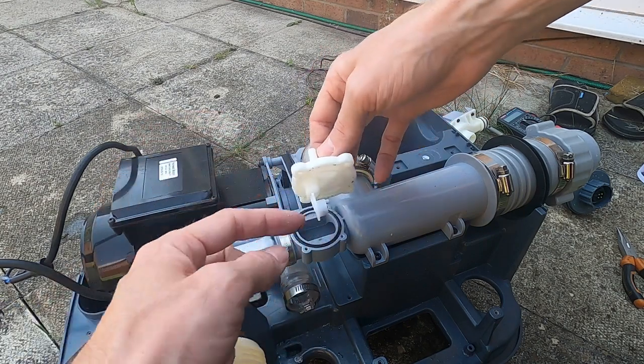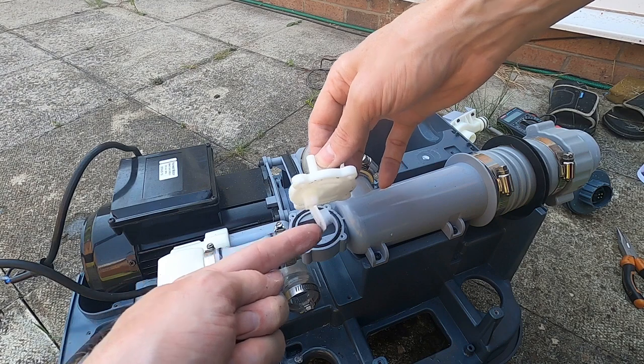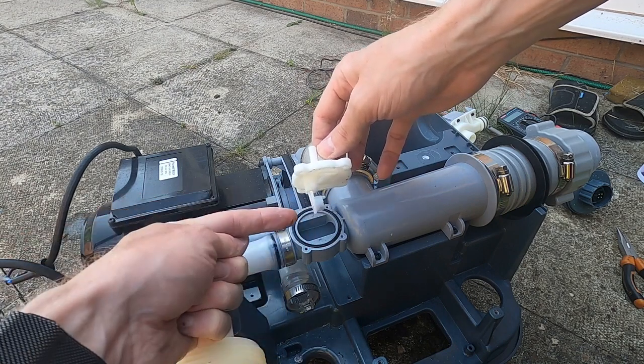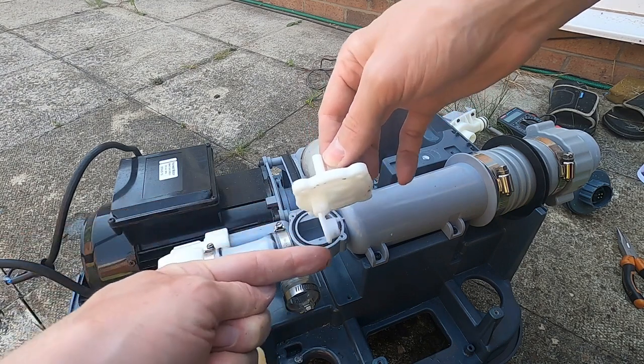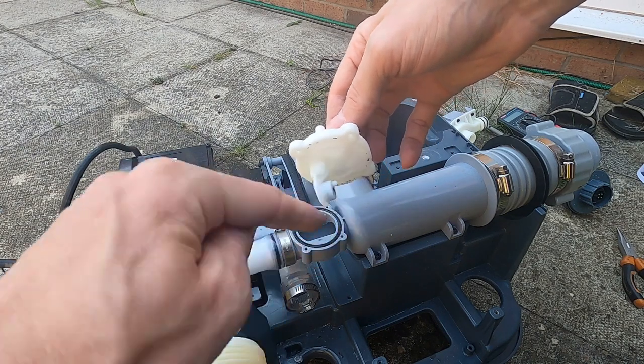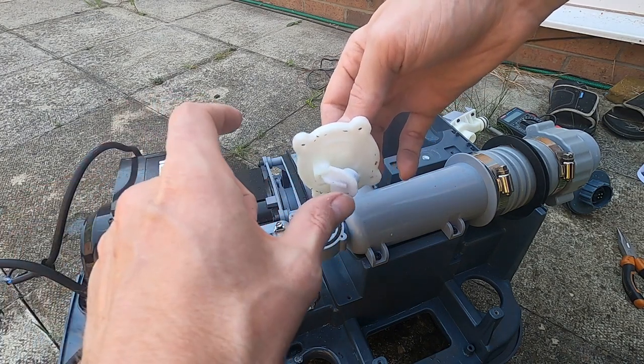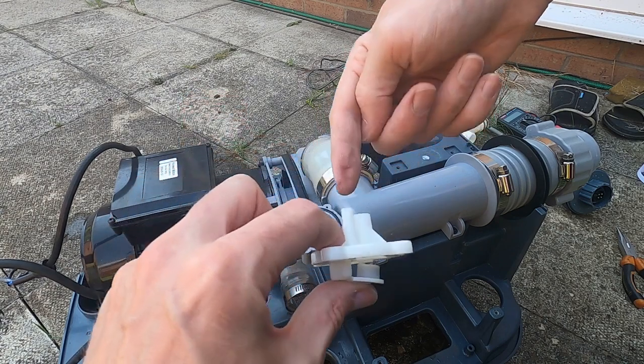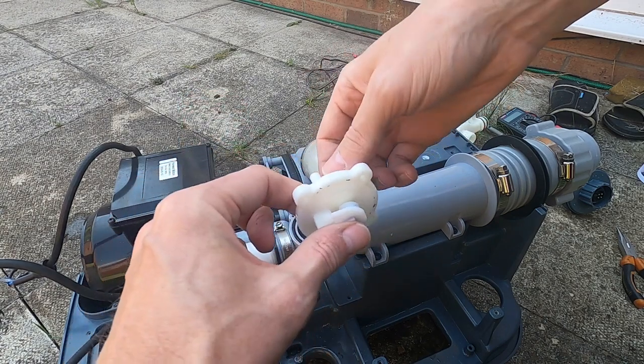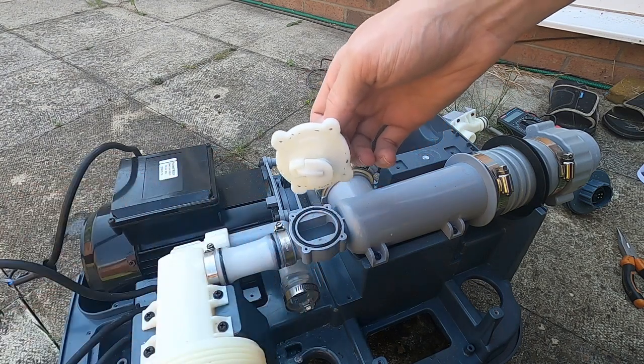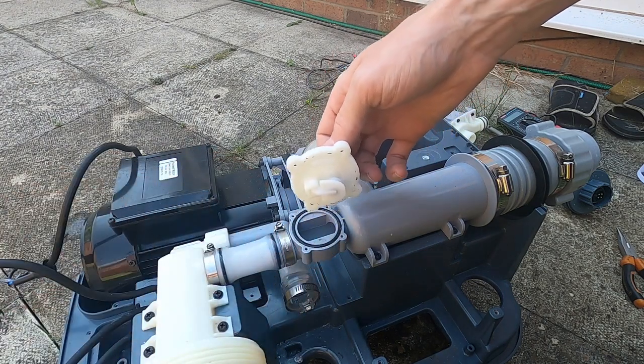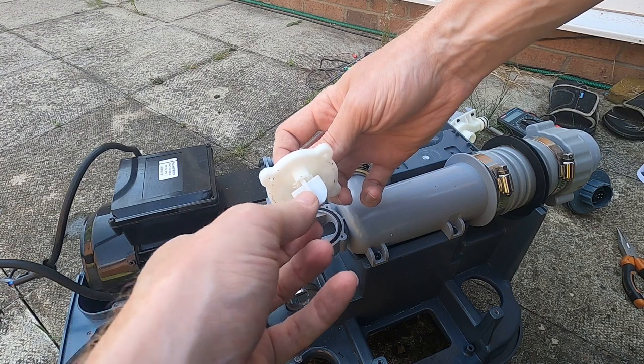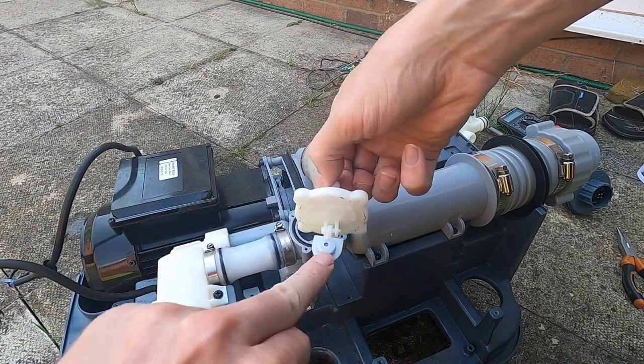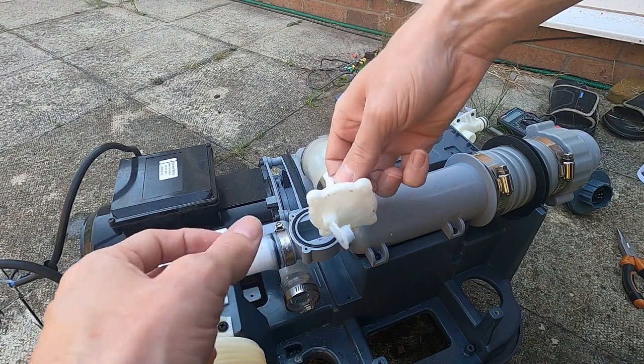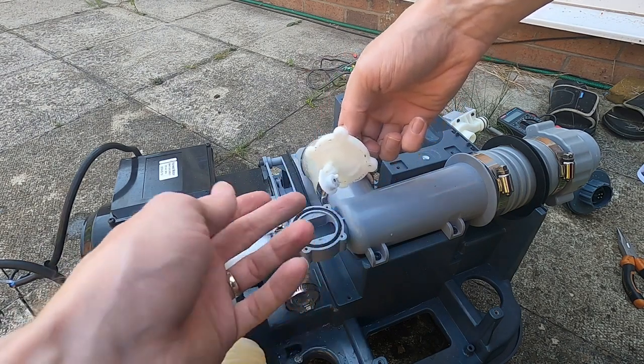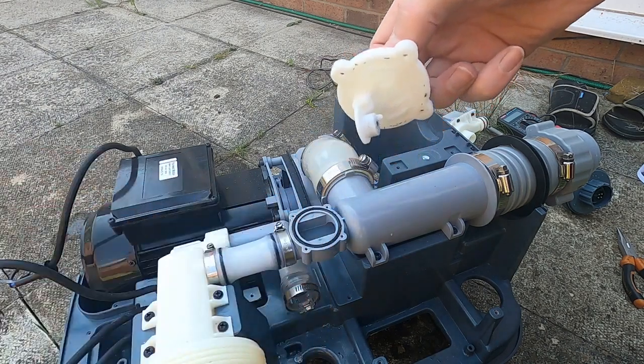When you take this off, pay attention to which way it fits. The water flow should push this little flap up, and inside there's a magnet - when that magnet is up near the top, that little black sensor pushed in the top detects it, and that's what tells the controller water is flowing through happily. So if any of this is damaged, or you see the magnet has cracked or anything like that, it'll need replacing. In this one, it just looks like it needs cleaned up and a new gasket.